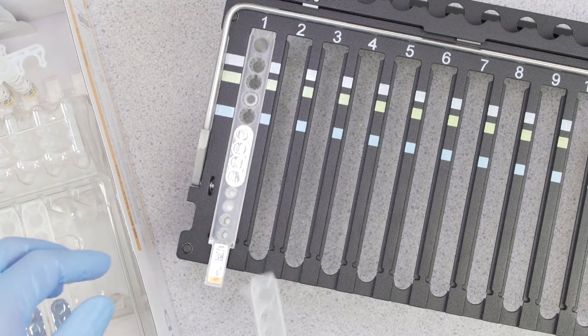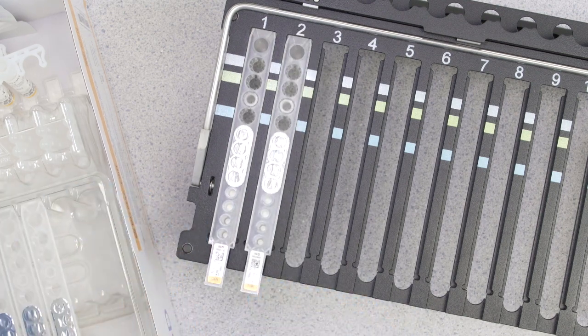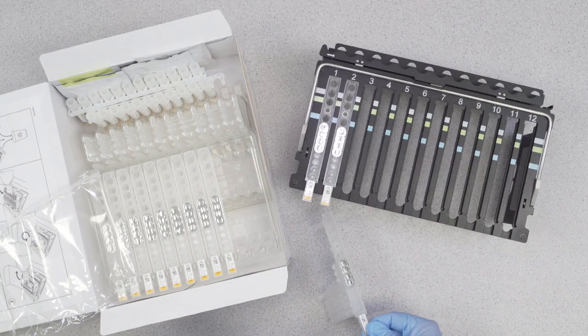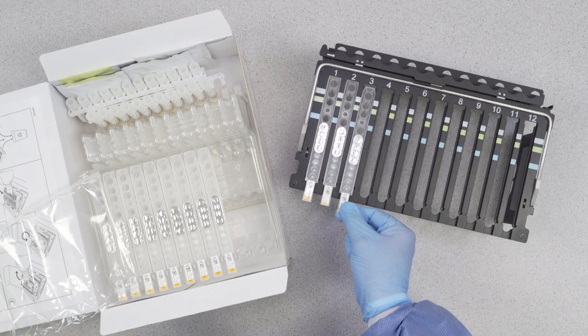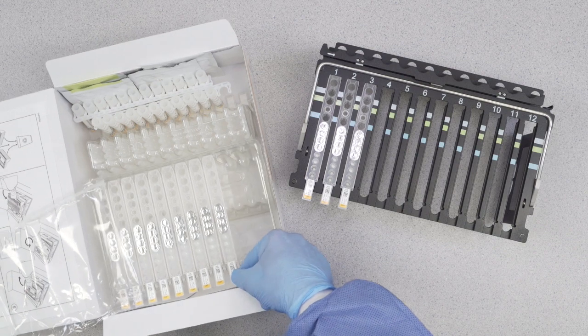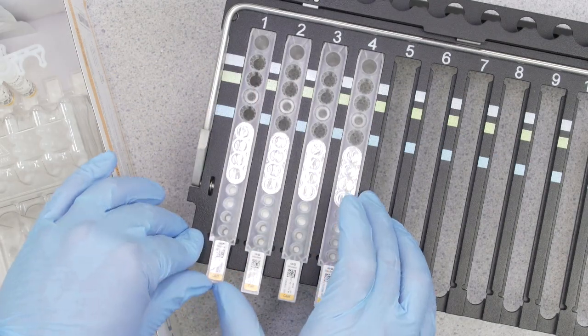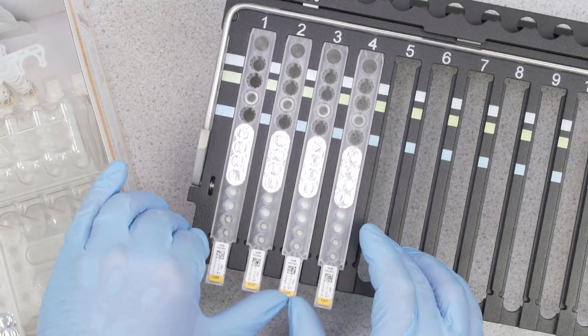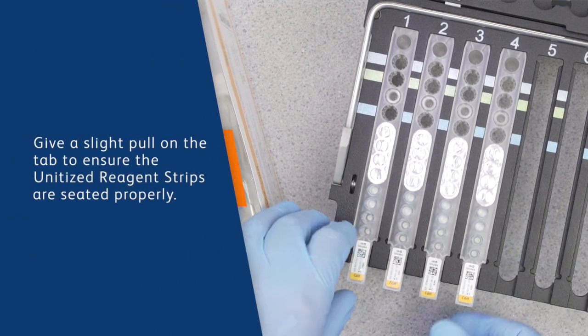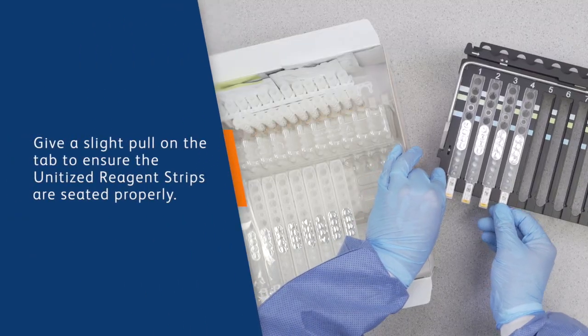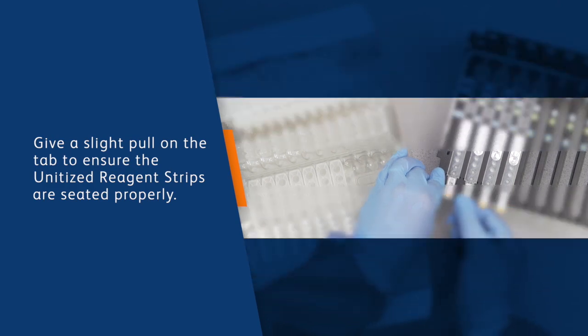For each sample to be tested, place one unitized reagent strip on the BD Max system rack. Once your unitized reagent strips are in place, starting from the back, just push the strips into place. You can hear it snap or pop. To make sure reagent strips are seated properly, give a slight pull on these tabs to test them.